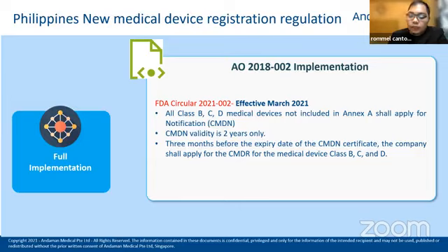In this circular, it mentions that all Class B, C, and D medical devices not included in Annex A shall apply for a notification, or a CMDN. CMDN validity is only 2 years, and 3 months before the expiry date of the CMDN certificate, the company shall apply for the CMDR for the Class B, C, and D medical device.